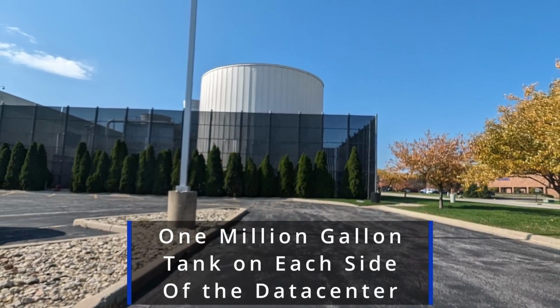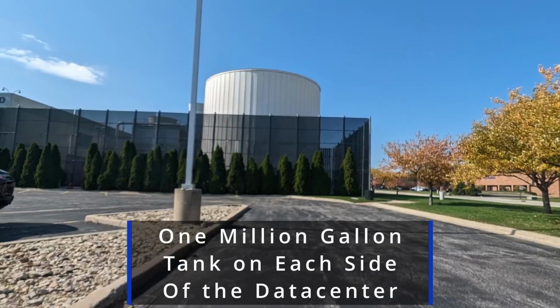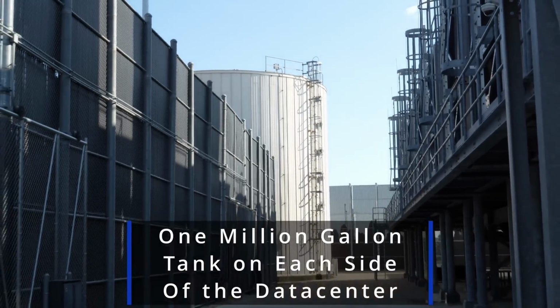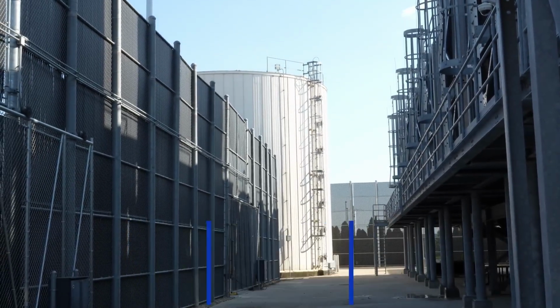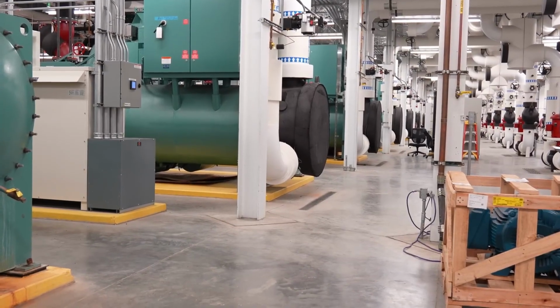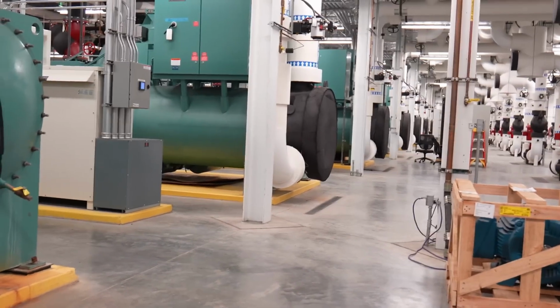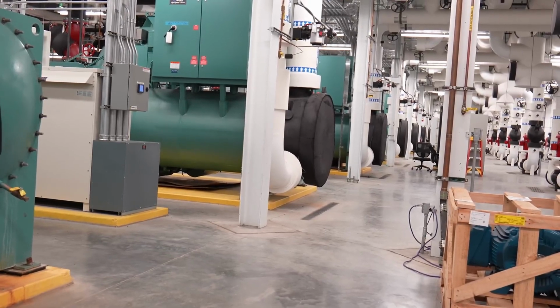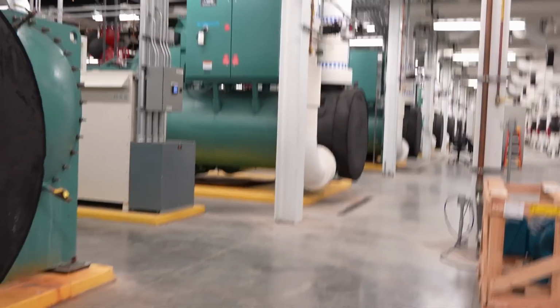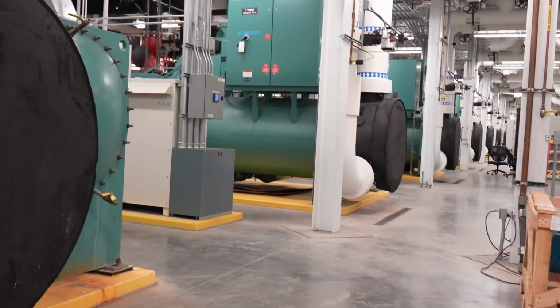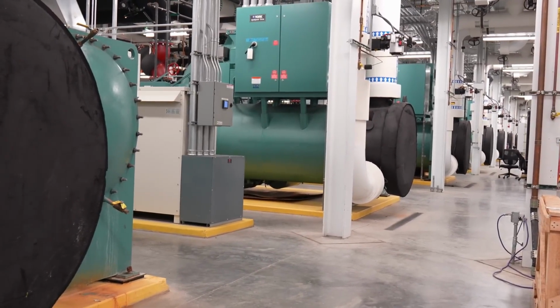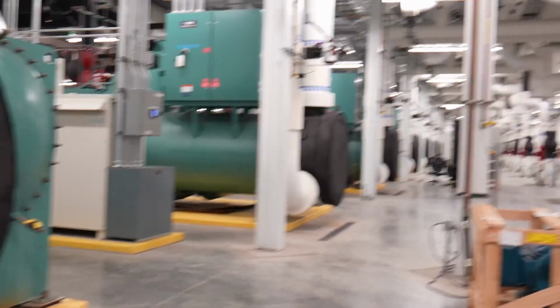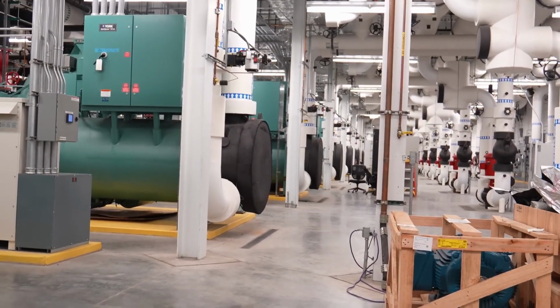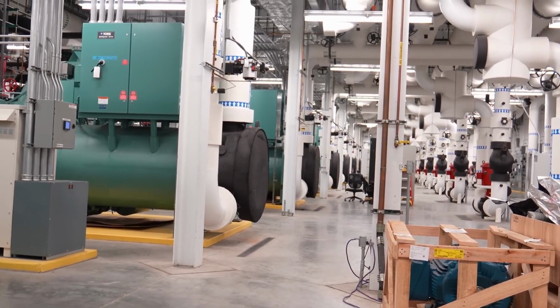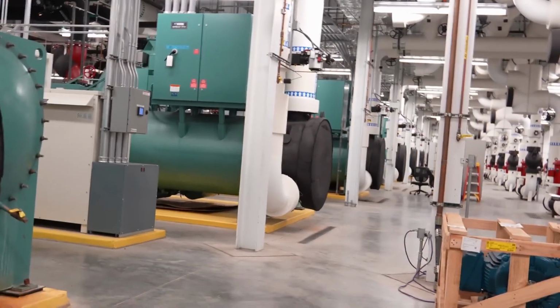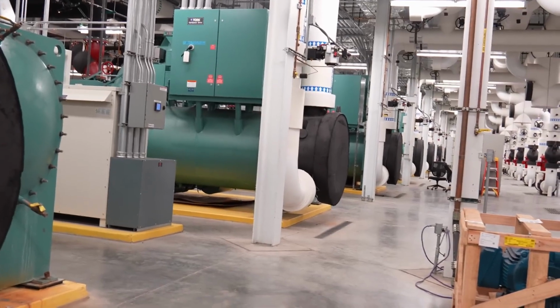Think of it this way: it costs a lot of money during the day to cool things down, since power is usually at peak, but at night it's a lot cheaper. So at night, when heat generation is still static but efficiency is really good, they cool down 1,000,000 gallons of water, dropping its temperature. Then during peak times of the day, instead of using the centrifugal chillers as much, they bring that cold water into the system as a heat transfer to help cool things down.